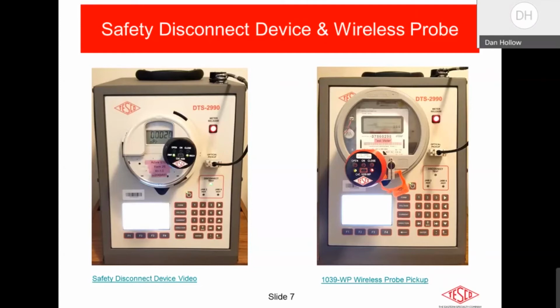I'm a big fan of LEDs when it comes to communications because it lets you know what's happening during a communication session and where the nature of the problem might be as a result of not seeing one of the LEDs flashing. You can say, oh, it's not responding, or I'm not getting any pulses from the optical probe, which means maybe there's something wrong with the optical probe. Maybe you haven't configured the vendor software properly to use the correct port that the optical probe is connected to. So there are a lot of good reasons to have LEDs to let you know what's going on in the interest of troubleshooting any communication problems you may have.